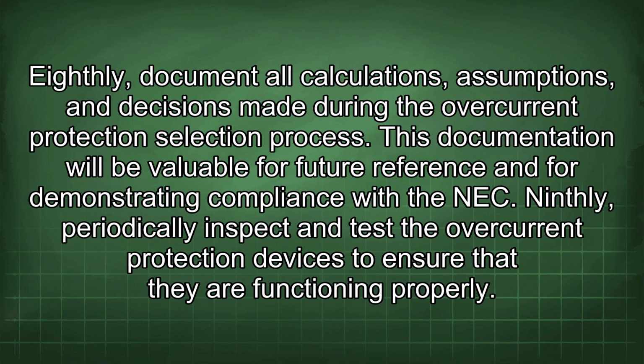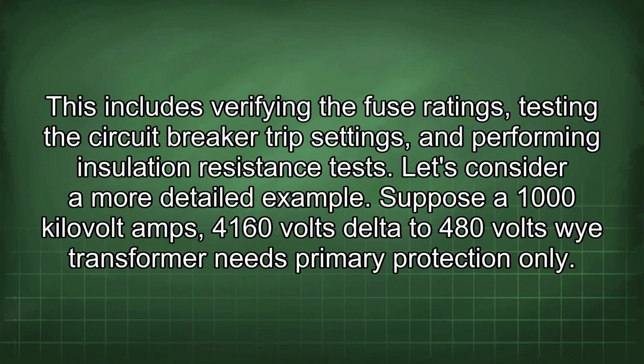Eighthly, document all calculations, assumptions, and decisions made during the overcurrent protection selection process. This documentation will be valuable for future reference and for demonstrating compliance with the NEC. Ninthly, periodically inspect and test the overcurrent protection devices to ensure that they are functioning properly. This includes verifying the fuse ratings, testing the circuit breaker trip settings, and performing insulation resistance tests.